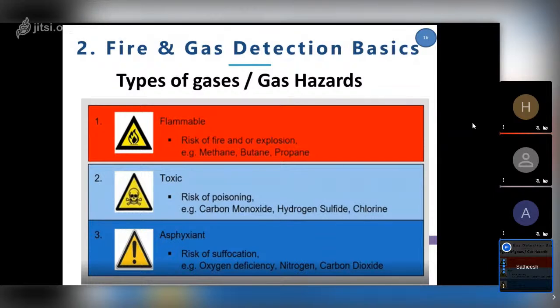Finally, asphyxiant gases. This is very important because oxygen is essential for breathing. We have oxygen gas detectors to ensure the oxygen level in a room or plant is good, so we have enough air to breathe. Nitrogen and carbon dioxide are also monitored because when there is a leak of nitrogen or carbon dioxide, they displace oxygen and the oxygen level goes low. So we are trying to keep oxygen at an optimum level.